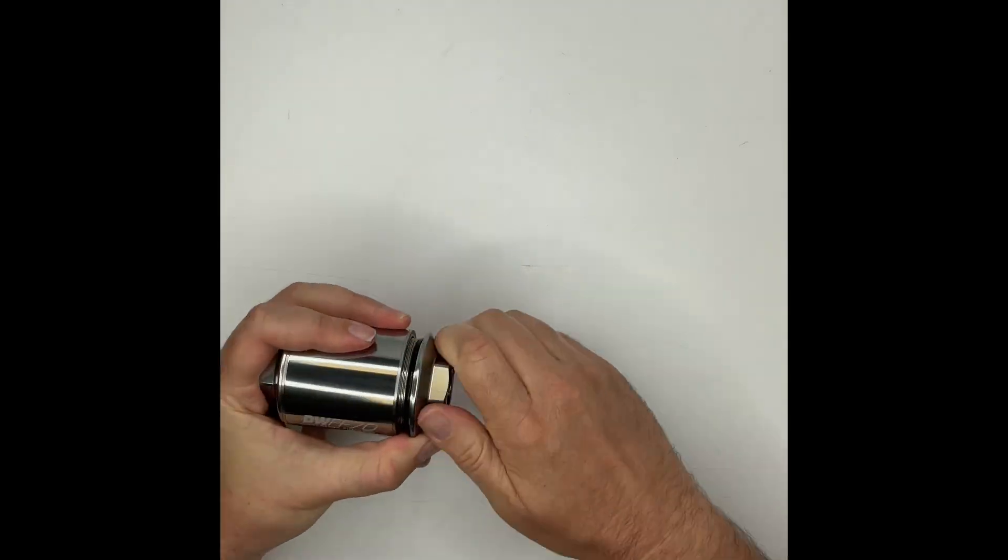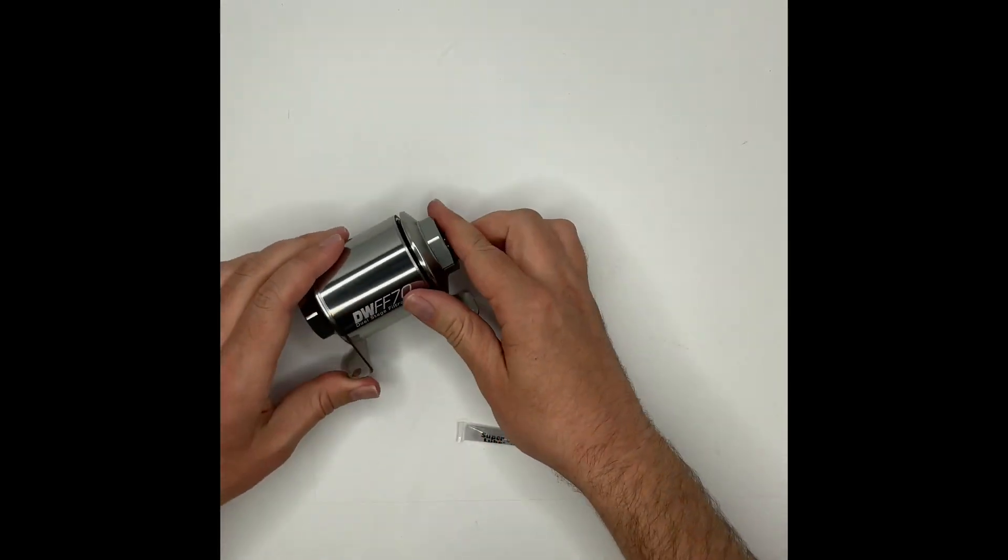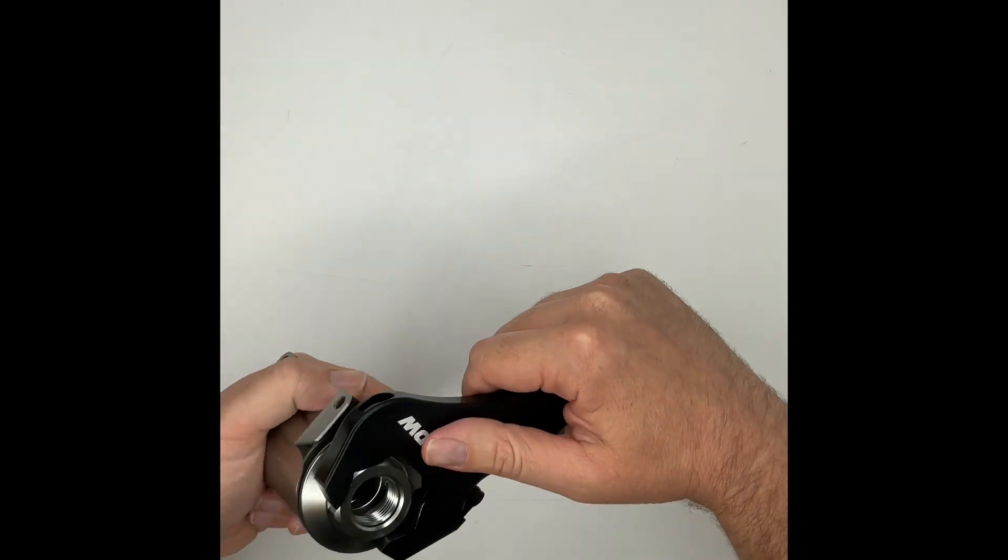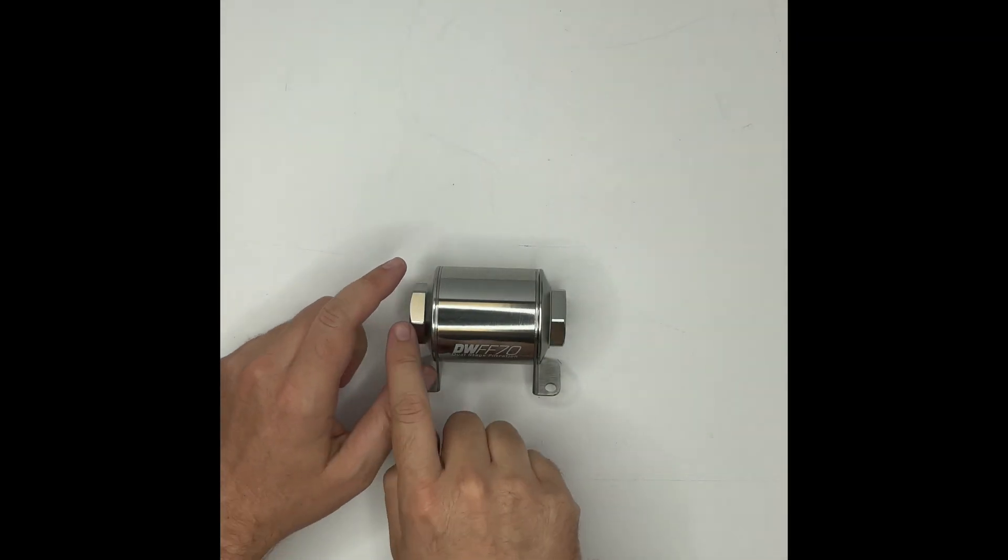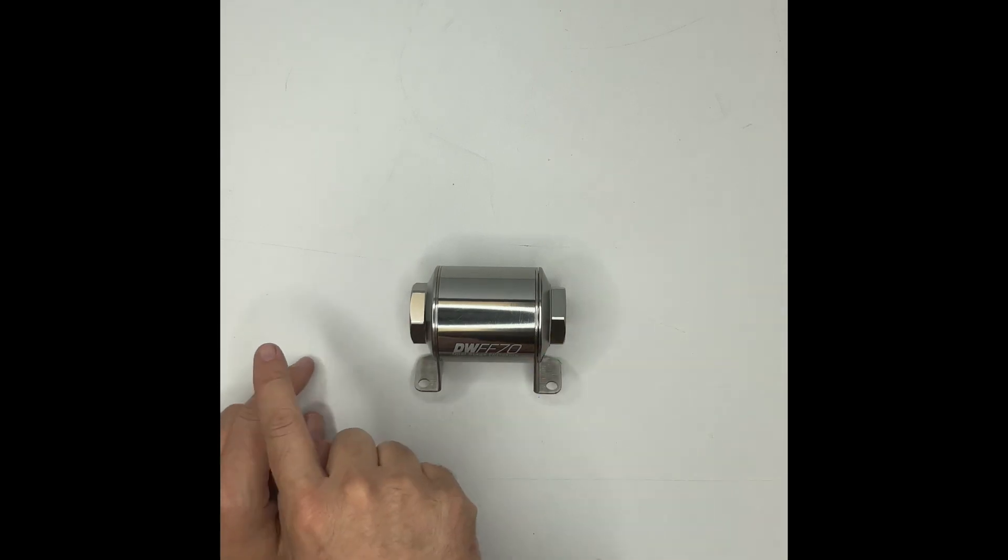After assembly, torque both caps to 15 to 20 pounds. Don't over tighten as this could cause leaks. It's important to note that the way that we have assembled this filter is so that the fuel will flow from the left to the right. It can be assembled in either direction.